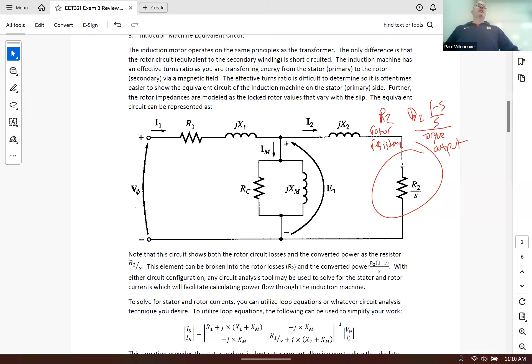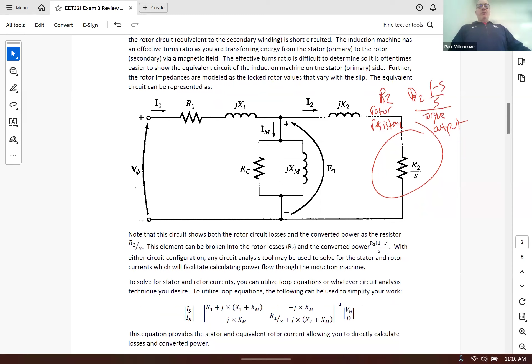But under really small slip conditions, R2 times 1 minus S over S is going to limit the amount of rotor current, which means it's going to limit the rotor losses. R2 represents the rotor losses, I squared times R2 is just heat, so the lower that current, the less loss and the more efficient the motor is. It doesn't really affect the power output though, because if R2 is sky high, I squared times R is still going to be a pretty high number. So I don't need a lot of current to drive a lot of power, particularly if that resistance value is really, really high. That's why it's really helpful sometimes to break the terms up.